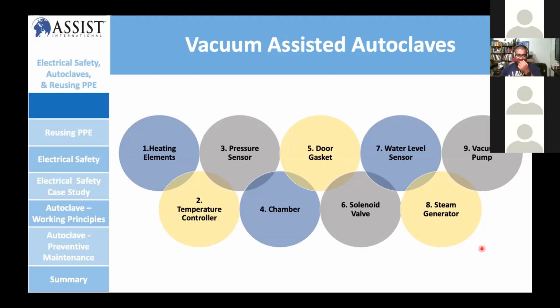In most of the places that I have been traveling, like some hospitals, there's always an issue with the vacuum pump because of certain issues. What happens is the vacuum pump is not working properly. Sometimes the steam generator is not working properly due to the water condition. When the vacuum pump doesn't work properly, you don't get proper heat. So inside the chamber, you're not going to get equal heat. So all these are some of the common problems. In some places the door gasket is leaking, so eventually you don't create proper pressure. So you have to look into this particular device. Some of the components have to be taken care of to make sure it works properly.